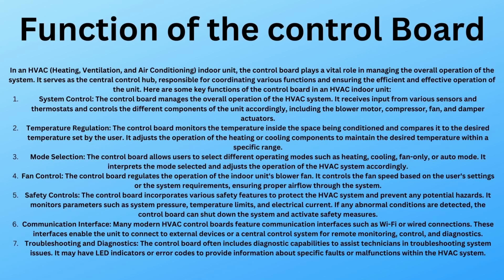Okay, well, let's go ahead and go over the functions of the control board. The reason why we call it a control board is the thermostat itself goes into the control board that's in the indoor unit, either an air handler or a gas furnace. The reason we're starting with this first is because you need to know how this fundamentally works and where the starting point of your thermostat goes to your indoor unit to the outdoor unit, and how it fundamentally operates as a one unit system.